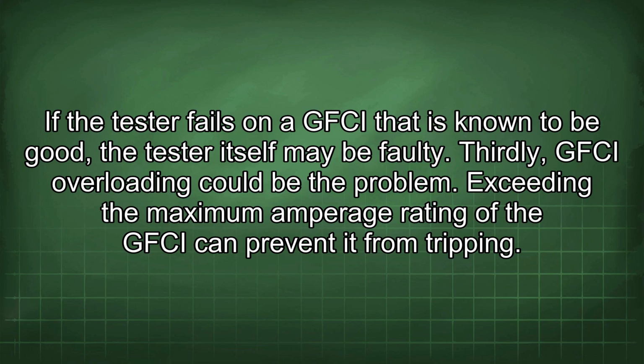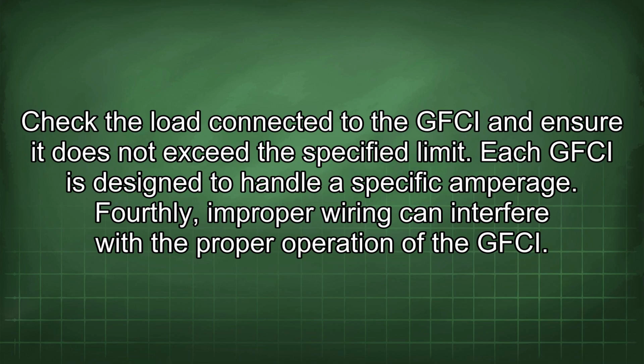Thirdly, GFCI overloading could be the problem. Exceeding the maximum amperage rating of the GFCI can prevent it from tripping. Check the load connected to the GFCI and ensure it does not exceed the specified limit. Each GFCI is designed to handle a specific amperage.